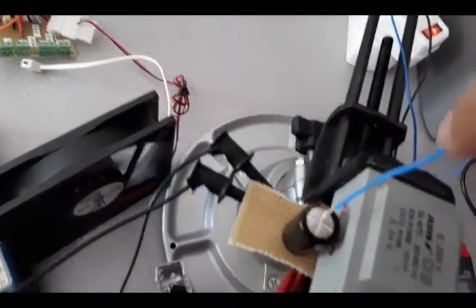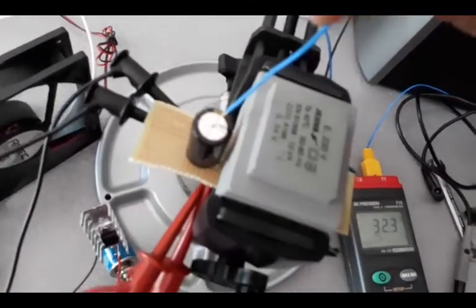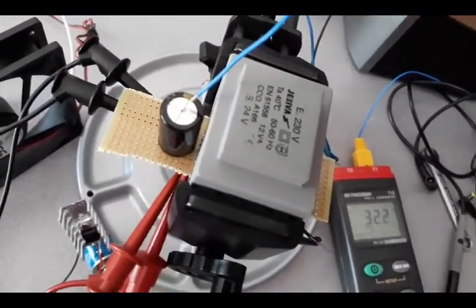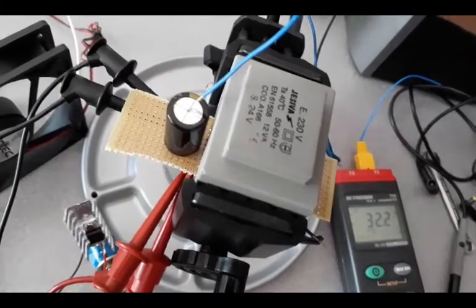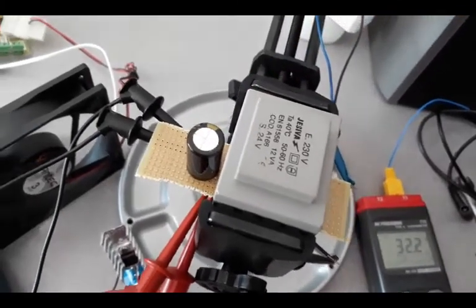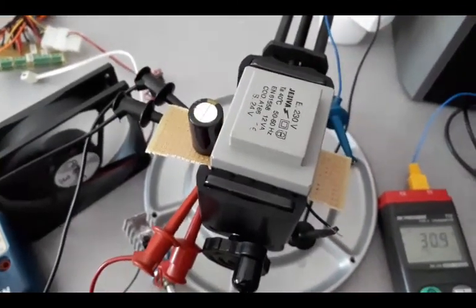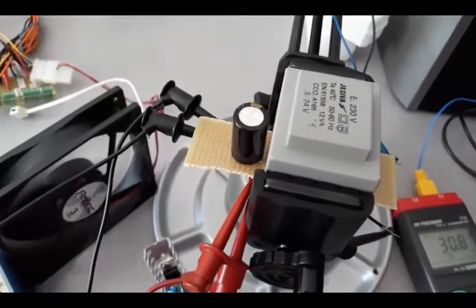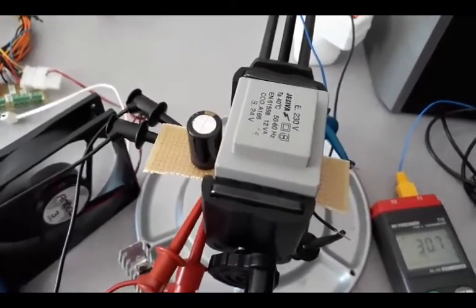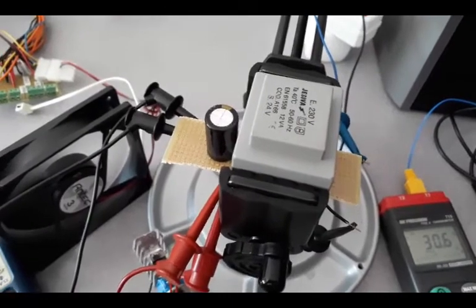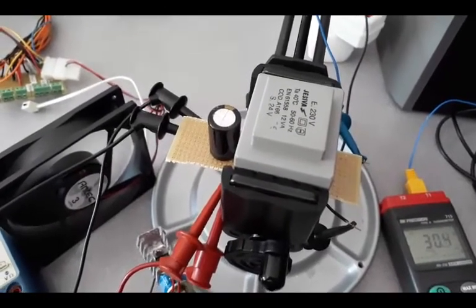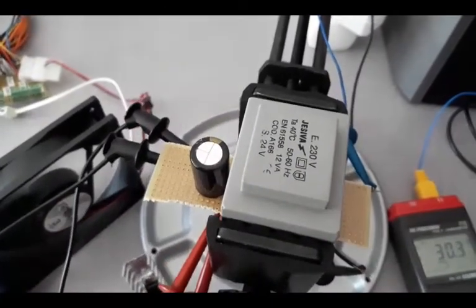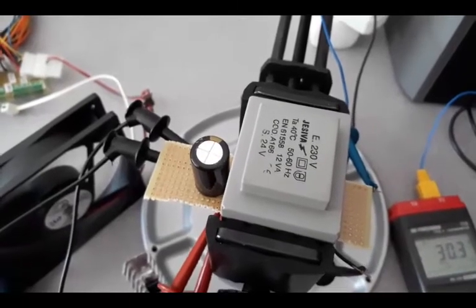Probably more interesting is to look at the aluminum electrolytic capacitor, which is about 32 degrees. So overall, this power supply isn't heating up much at all. The two critical components are only maybe 2 to 3, perhaps 4 degrees higher than ambient temperature, and they're below the 40 degrees C maximum listed on the transformer.